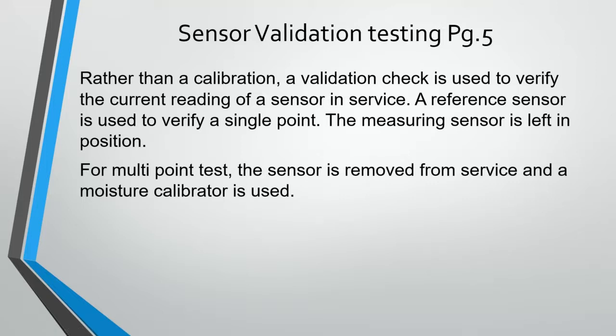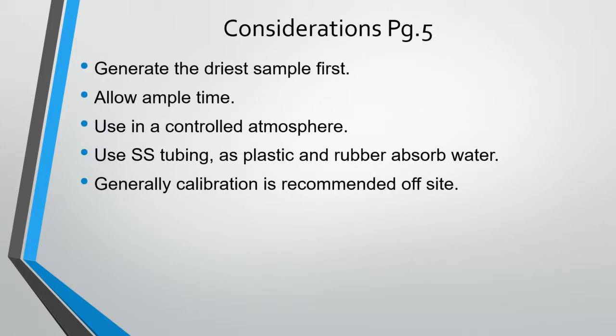Some considerations when performing dew point calibrations: start with the driest sample first — it's easier to add moisture than to remove it afterward. Be patient and give the analyzer ample time to stabilize. Use a controlled atmosphere, since temperature and pressure affect moisture readings. Use stainless steel tubing, as plastic and rubber can absorb water. As a general rule, it is recommended to calibrate off-site if you can.